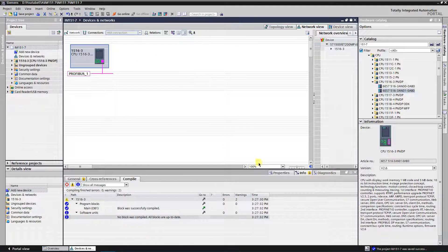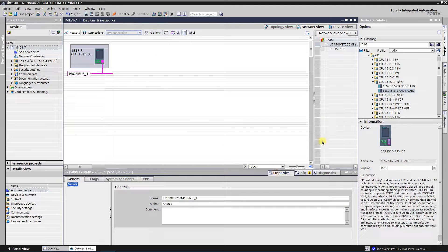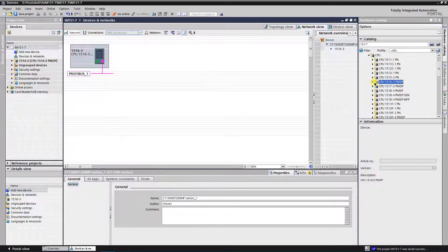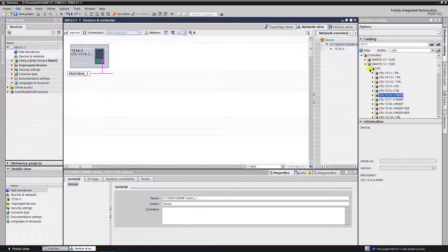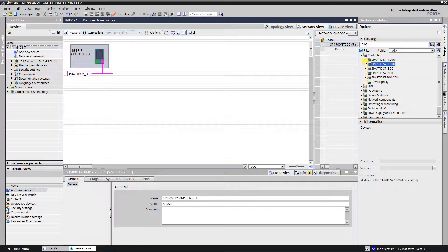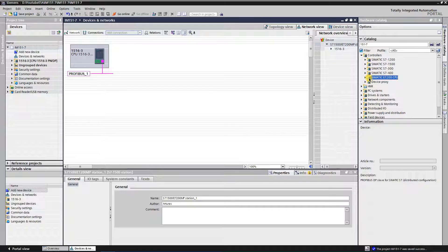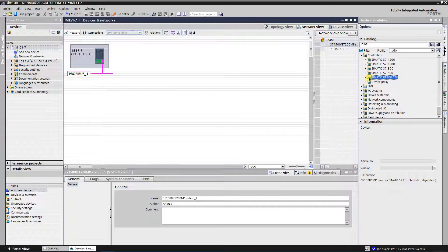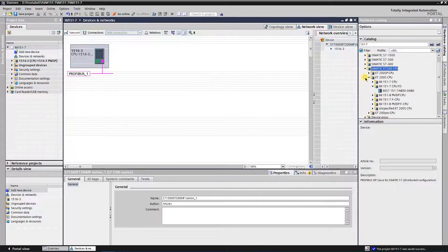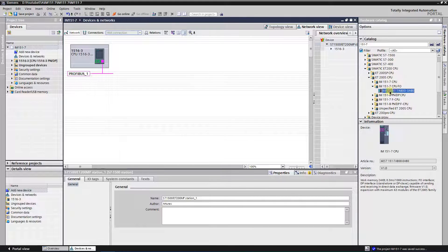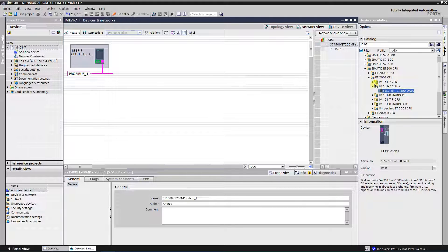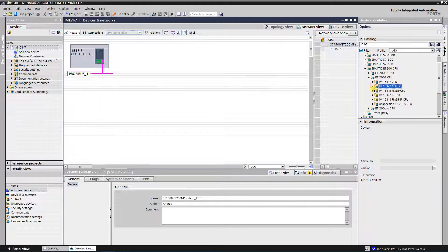Now let's add slave CPU, IM151-7. Find SIMATIC ET200 CPU folder under the controllers in the hardware catalog, and expand it. Find the right folder of your CPU, expand it, select the CPU version and drag and drop it onto the same window as your master CPU.